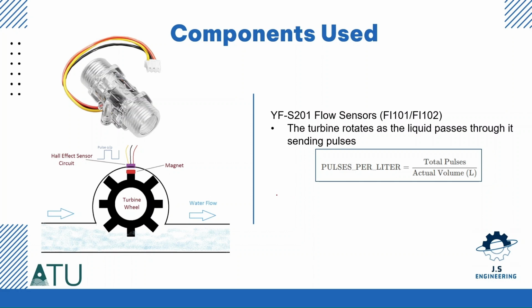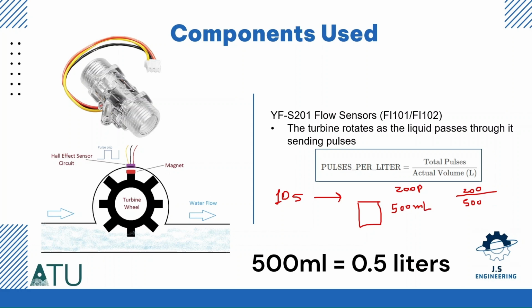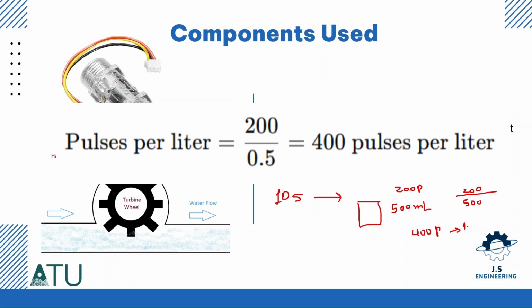So another test could be to allow the pump to run for 10 seconds. Measure how much water passed by the sensor on a jug. Use a scale. For example, you have 500 milliliters. You had 200 pulses. So your calibration factor will be total pulses, 200, divided by actual volume, which you measure with a scale, so it will be 500. So I know in every 400 pulses will be 1 liter.